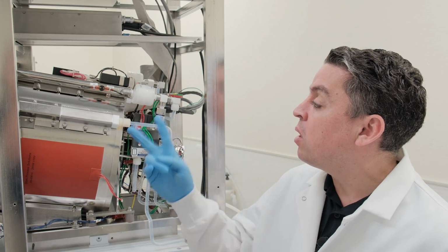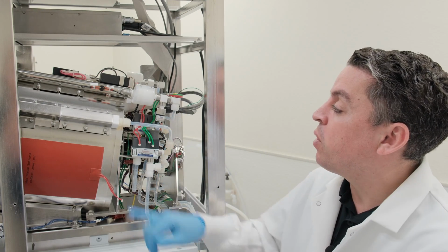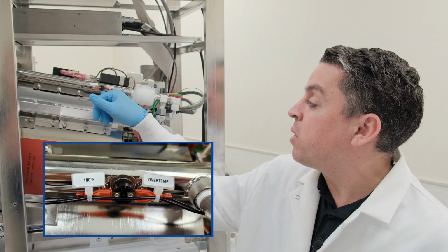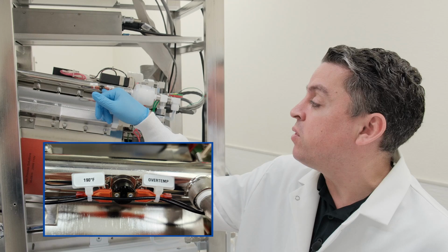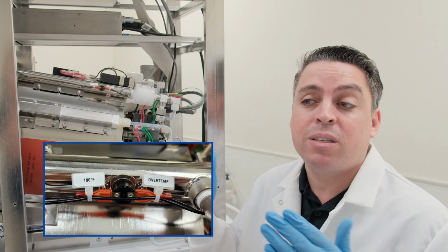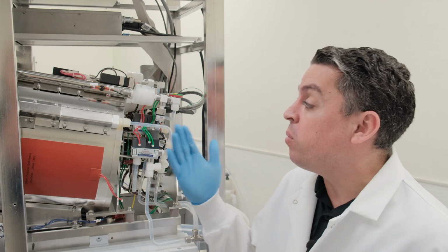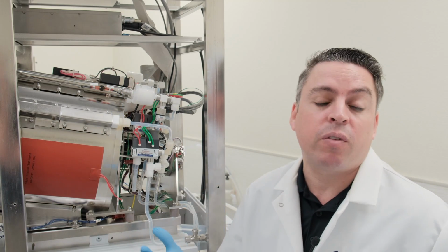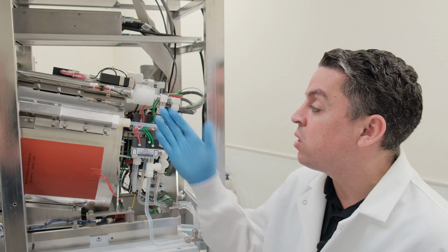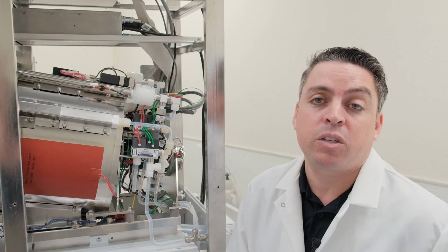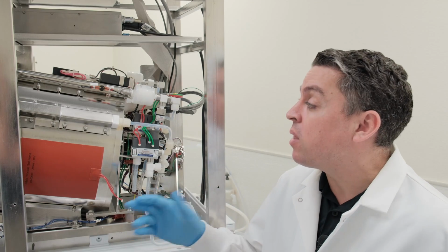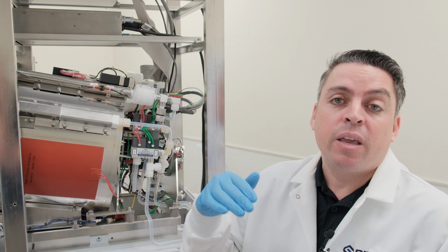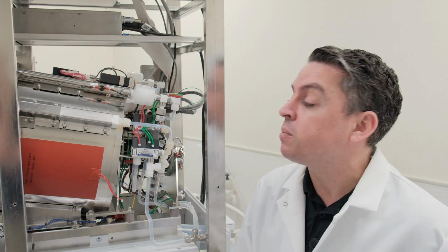The 2 uncommon causes are going to be, first, our overtemp switch right here failing. Typically, it won't have failed. What it'll have done is actually opened once and then got stuck open. So that would mean that you actually had some kind of overtemp condition on here, and that's something you'll have to investigate further into as well to understand what caused our overtemp condition in the first place. Typically, that's going to be a flow issue because you didn't have enough flow, and that allowed the heater to get to that overtemp position.